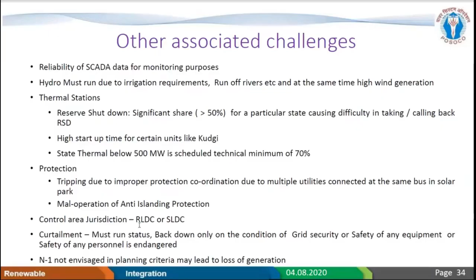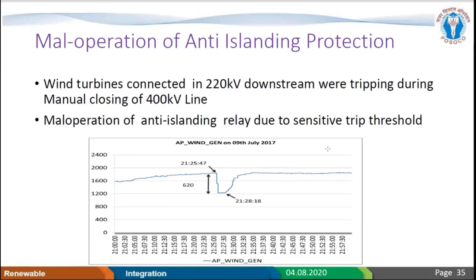One more problem we encountered is anti-islanding protection. There is an anti-islanding scheme, meaning they are not supposed to operate in islanding mode, at least as of now. So whenever something happens in the grid, this anti-islanding protection comes into picture and trips. But we observed that even while charging the 400 kV line, this relay was getting activated and tripping, because it was too sensitive. Now it has been corrected across the southern region.